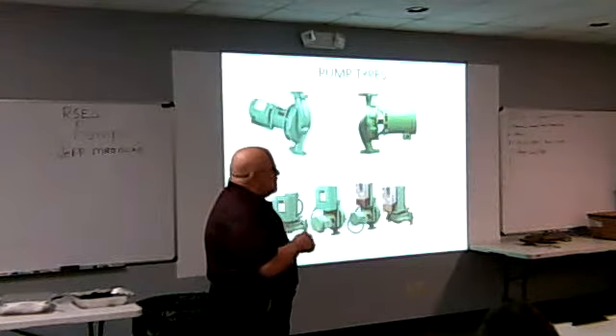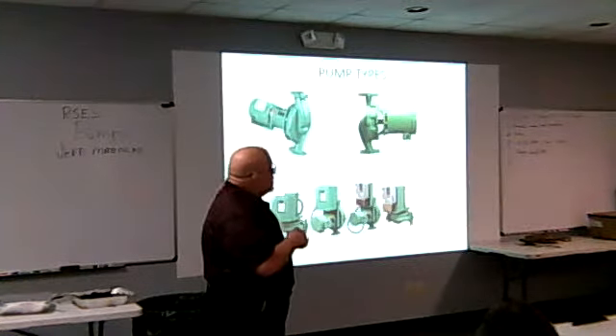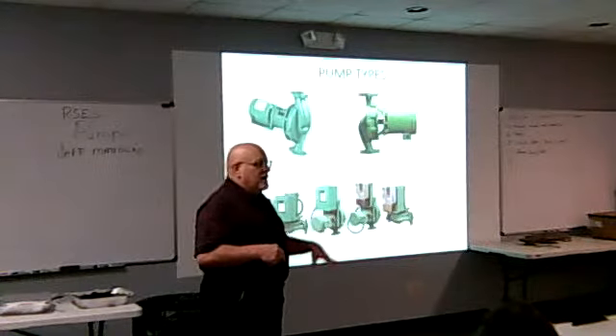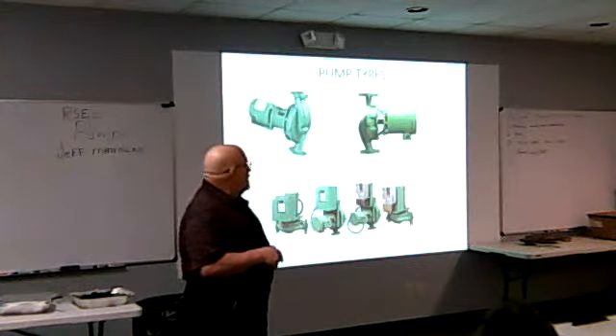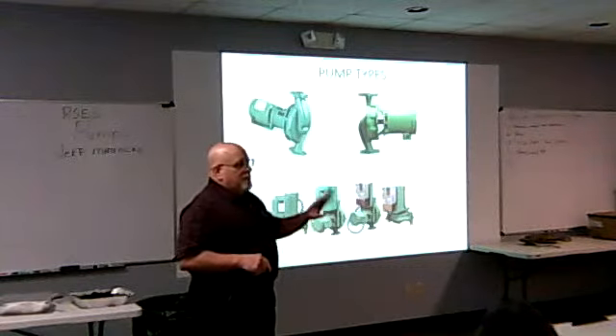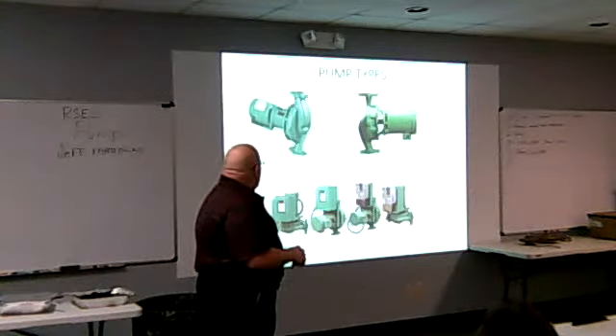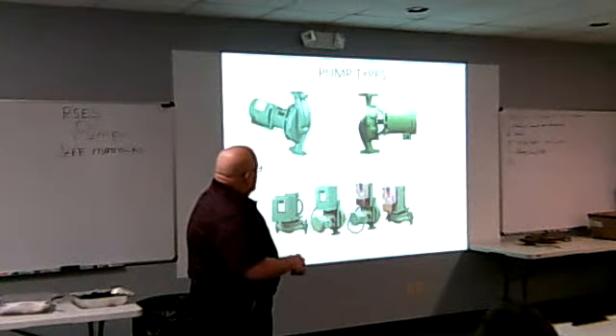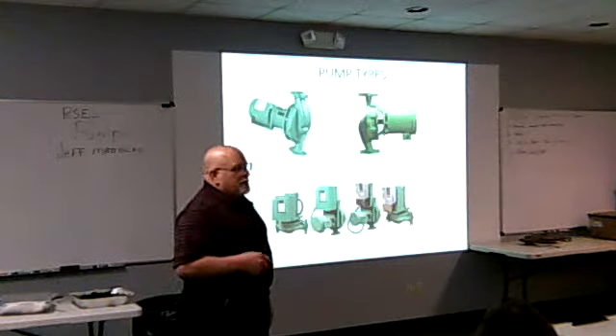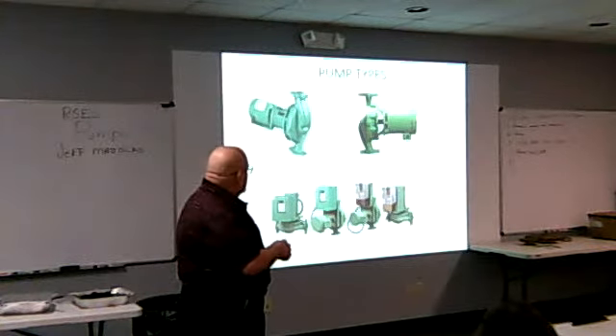These have to be mounted this way. If it says horizontal, that means this is parallel to the ground. It has to be mounted that way. You can't flip it up on end. These can go either way. That's the benefit of them. And then we can also get these with the VFD built in right from the factory. So if you need a VFD application, they come with it.